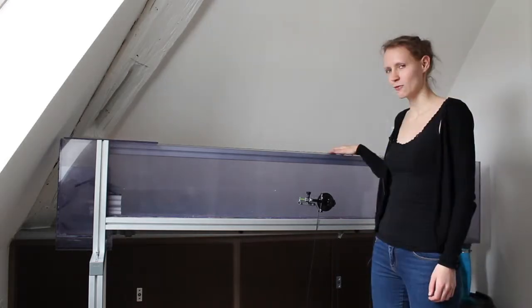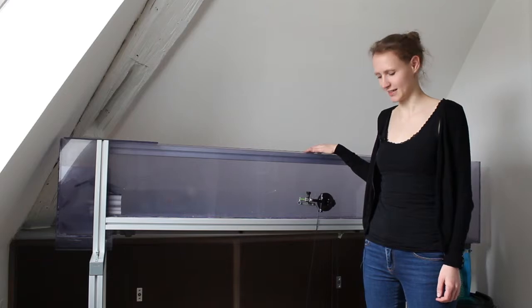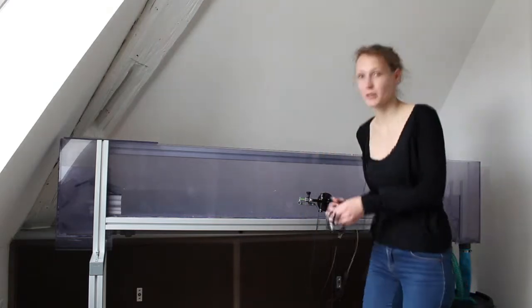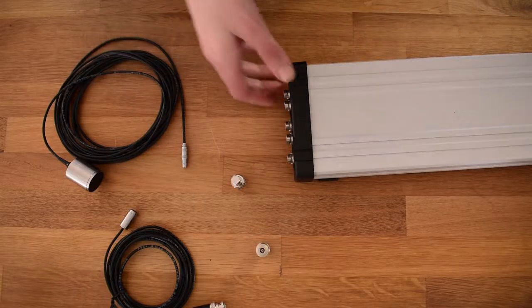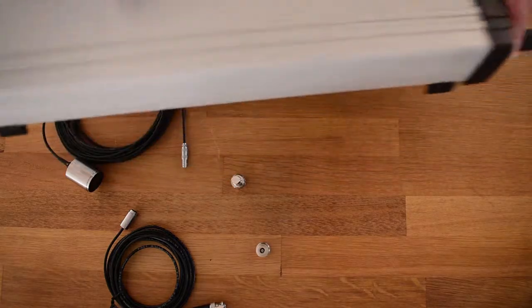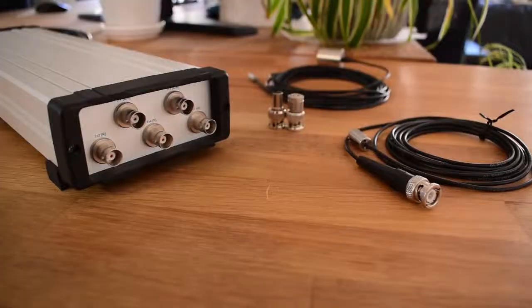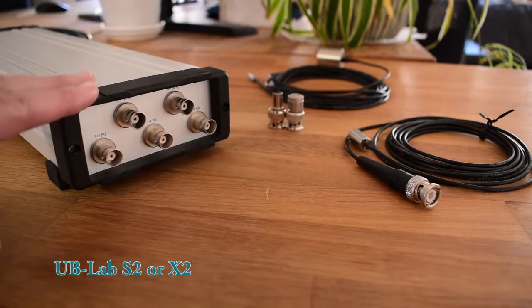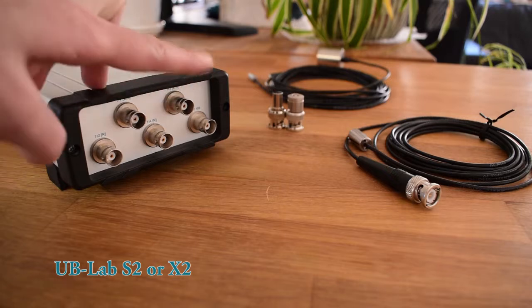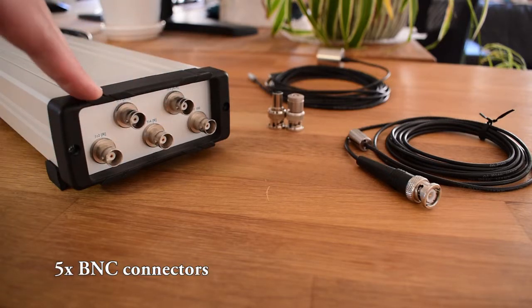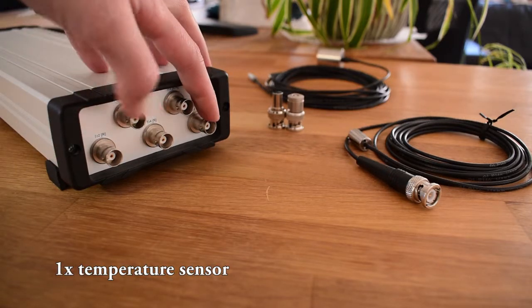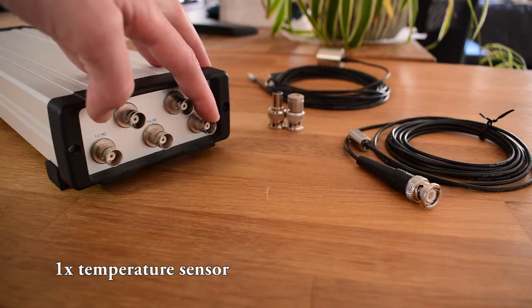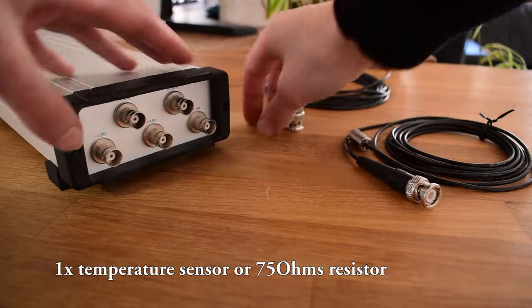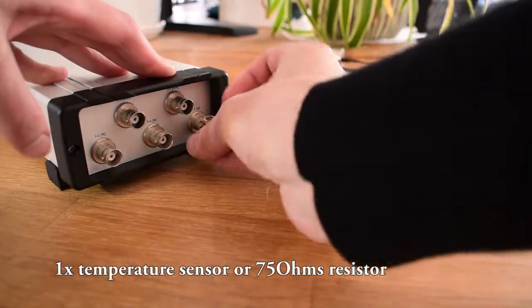Now you have installed your transducers on your setup. What do you need to do on the device's side? Well, you need to plug your transducers, of course. The UB Lab, you have wired it before as shown in the video given in the description below. On the sensors interface of the UB Lab S2 or X2, you will find 5 BNC connectors. One is for a temperature sensor. If you do not use any temperature sensor, you have to plug a BNC 75 ohm resistor, or the measurements will be affected.